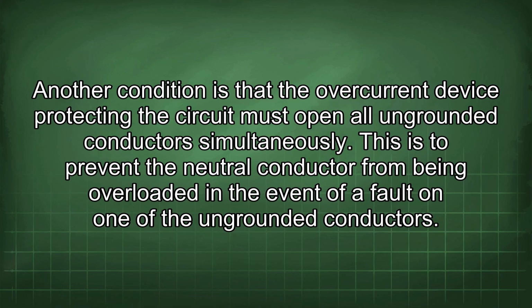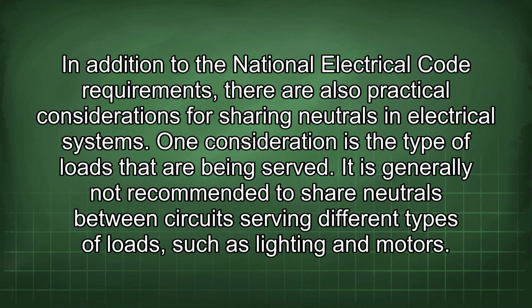Another condition is that the overcurrent device protecting the circuit must open all ungrounded conductors simultaneously. This is to prevent the neutral conductor from being overloaded in the event of a fault on one of the ungrounded conductors.